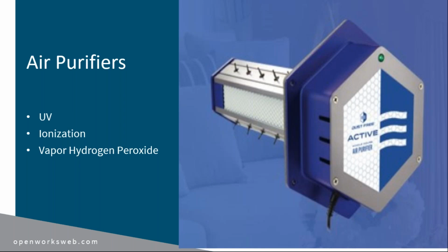Instead, UV lights are used to disinfect the inside of an AC unit itself. The inside of the HVAC unit is a very dark and moist place. This creates a breeding ground for bacteria and mold. By using a UV light positioned to shine on the evaporator coil, it can keep the inside of the AC unit clean and disinfected. UV lights work at their peak as soon as they are installed and start losing effectiveness over time. Bulbs will usually need to be replaced every 1 to 3 years, depending on the manufacturer's recommendations.